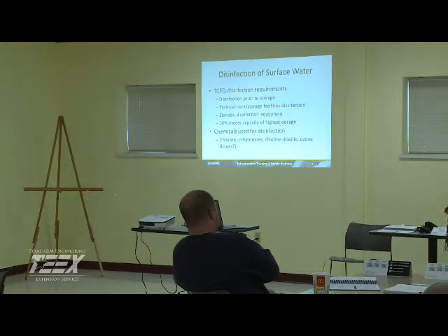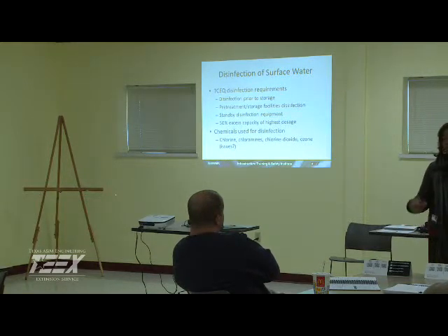Excellent. Chlorine dioxide. Who remembers the problems associated with chlorine dioxide? Chlorite, chlorates, and again here I have a maximum residual. I should not go over 1 milligram per liter because that's when I start having those formations, which are health issues. 0.8 is the maximum contaminant level for that.